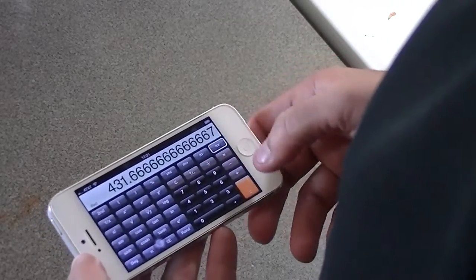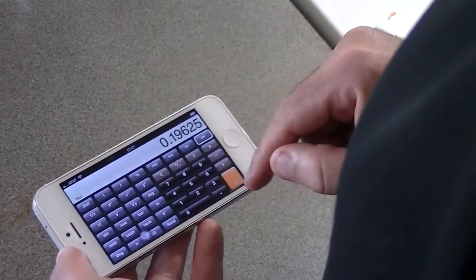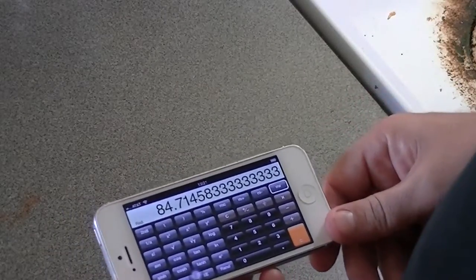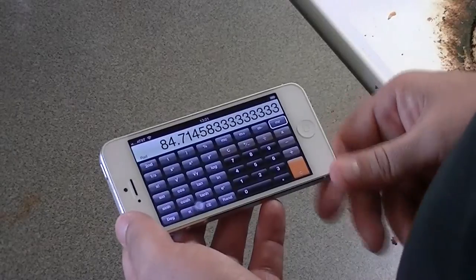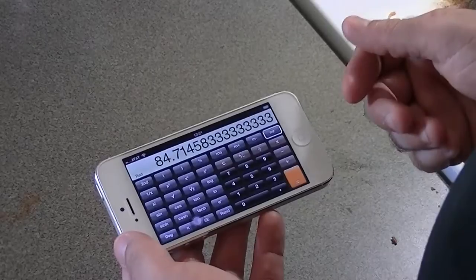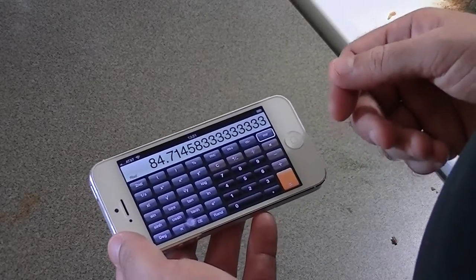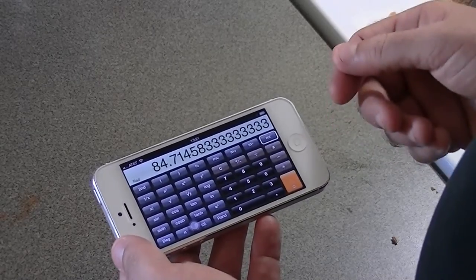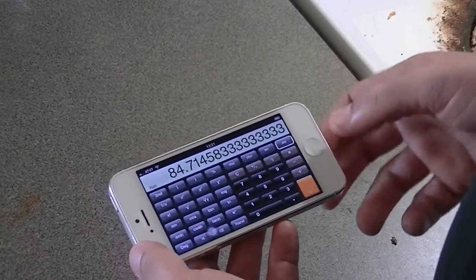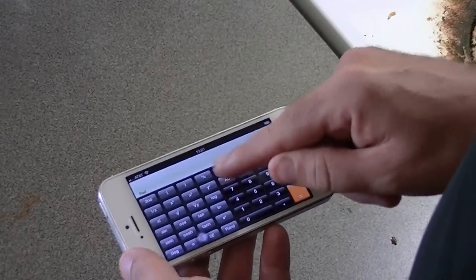If we recall memory times 0.19625, it gives us a flow rate of 84.71 cubic feet per minute. I'd probably call that 84. Remember this was on the high setting for the range hood and it should be moving 100, but it's actually moving 84 cubic feet per minute. This is very common—these kitchen range hoods are actually underpowered and aren't delivering what they should be delivering.